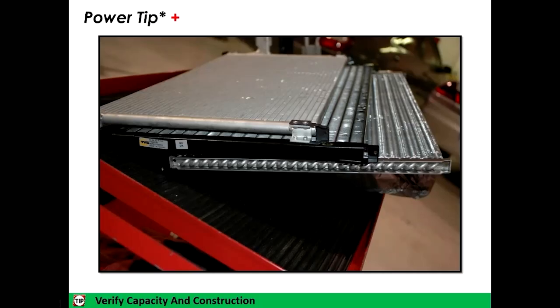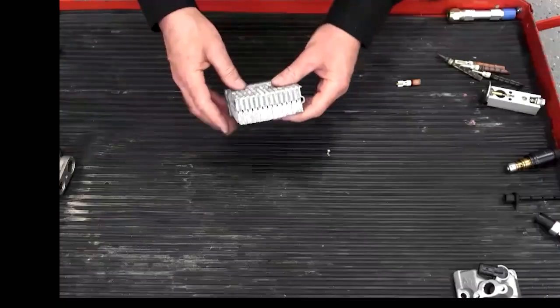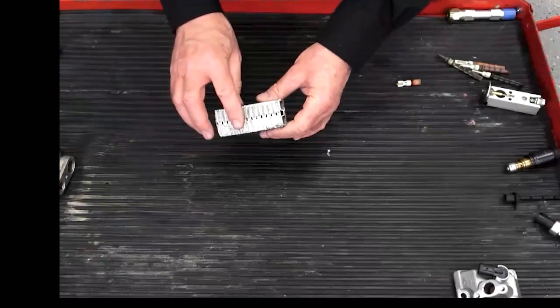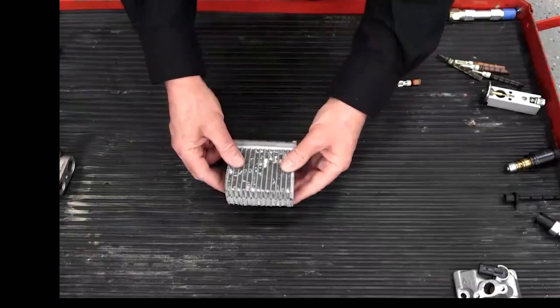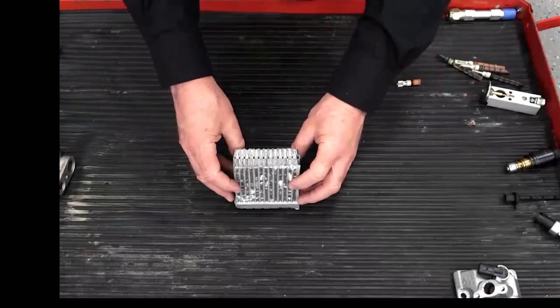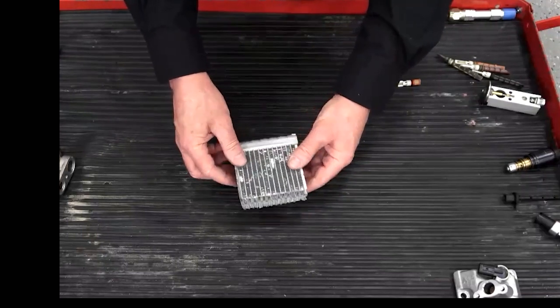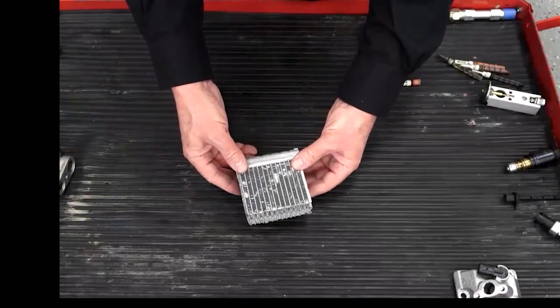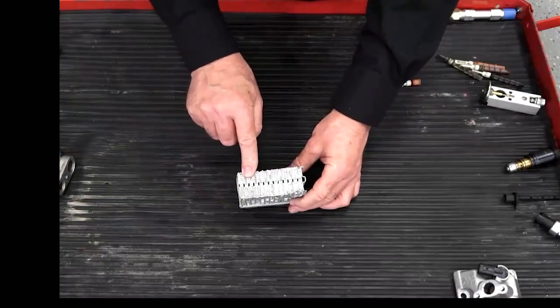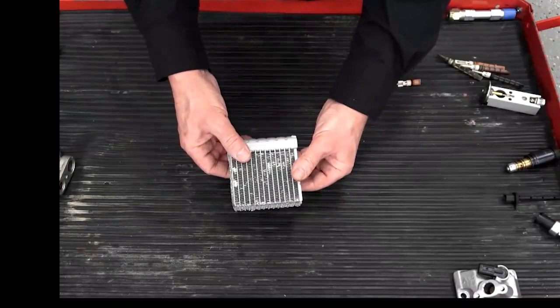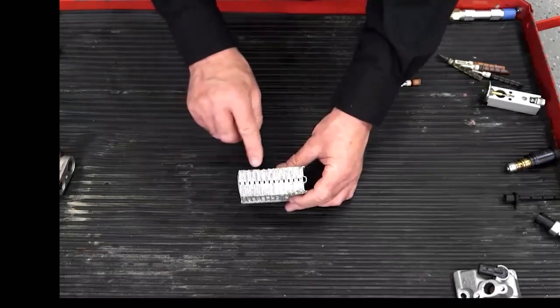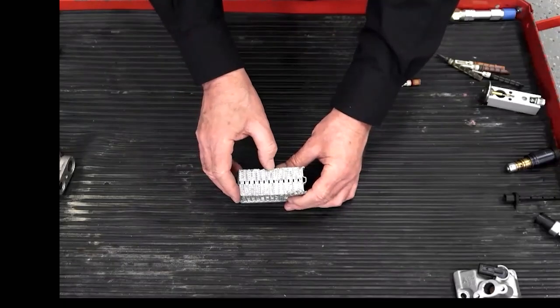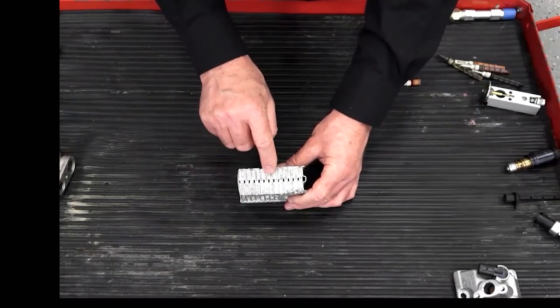Maybe not. I thought I had an actual cutaway of a condenser tube. Well, I will show you this. It's very close to approximate. This is actually a cutaway of an evaporator. And believe it or not, modern evaporators are the exact same design as the condenser. You can see looking in here, this is a flat tube multipass flow condenser. And when you look inside, you can see the little holes and the little passages here.